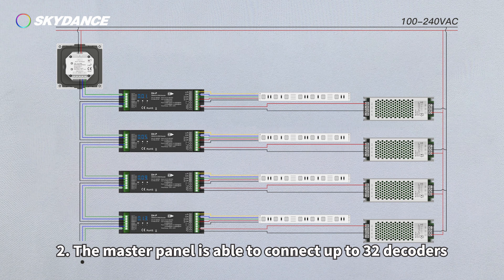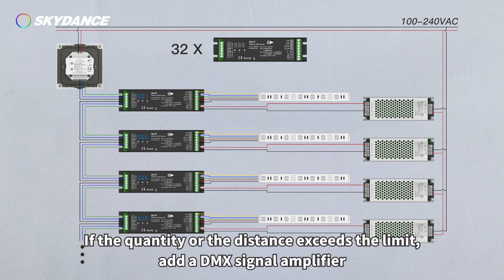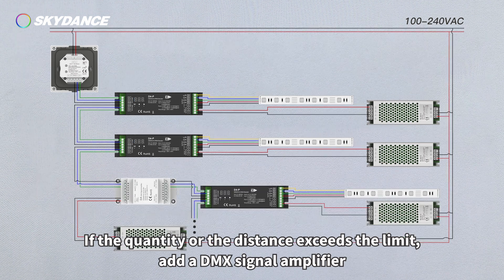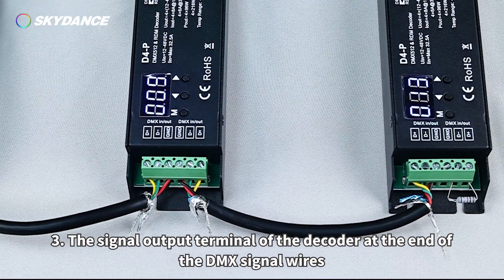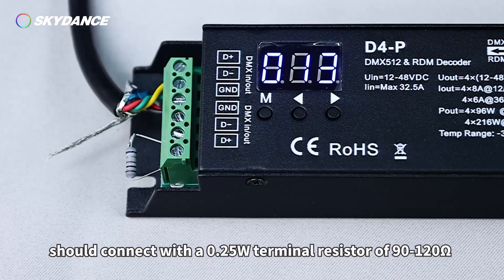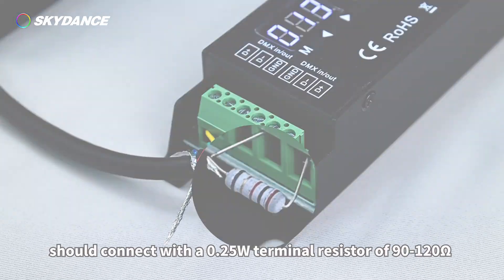2. The master panel is able to connect up to 32 decoders. Signal wires should be shorter than 150 meters. If the quantity or distance exceeds the limit, add a DMX signal amplifier. 3. The signal output terminal of the decoder at the end of the DMX signal wires should connect with a 0.25-watt terminal resistor of 90 to 120 ohm.